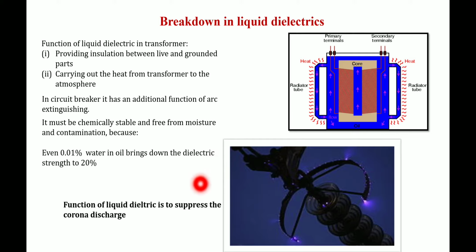That is the main function of liquid dielectrics. These liquid dielectrics have basic functions: first, they provide insulation; second, they act like a coolant; and they also suppress corona discharge. Corona discharge is a bluish glow that occurs around the pointed edges of a metal or conductor, due to ionization of the air media. Air is the perfect insulator between conductors, but due to ionization of this air, electrical discharge occurs in the form of this bluish glow, which is called corona discharge.